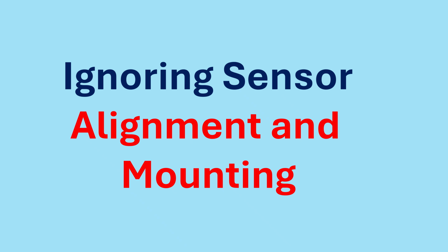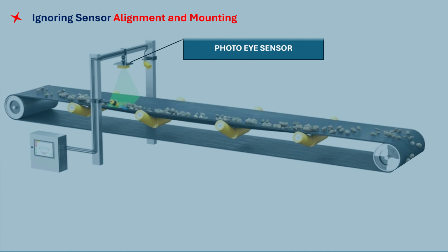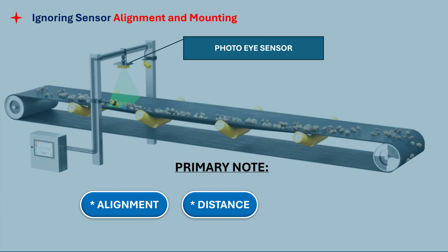Mistake number 6. Ignoring sensor alignment and mounting. Many sensors get replaced unnecessarily because no one checks their alignment, distance, or how securely they're mounted. Even a perfectly good sensor will stop working if it's positioned too far from its target, or slowly shakes out of place during operation. Mostly, electrical problems often start with mechanical issues. Primary note from mistake number 6. Verify sensor alignment, check sensing distance, and inspect mounting stability.